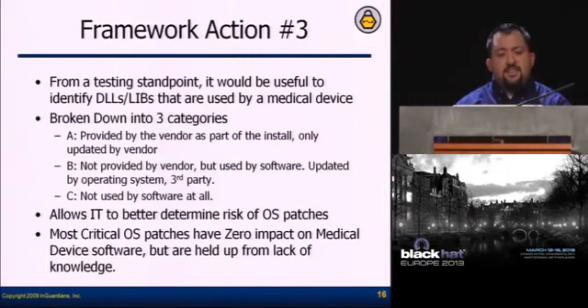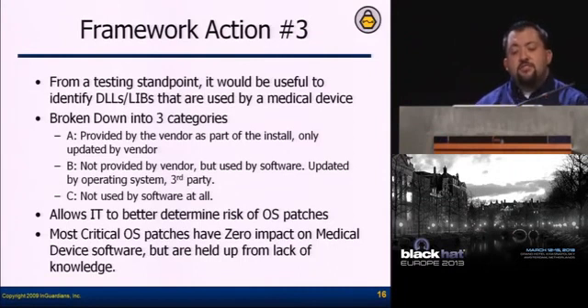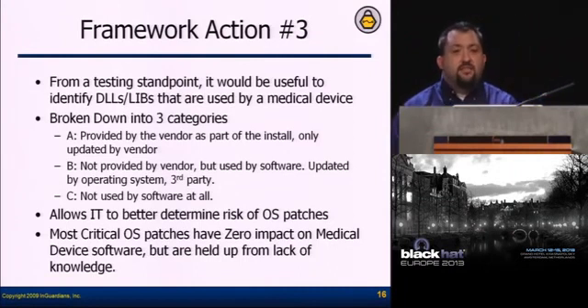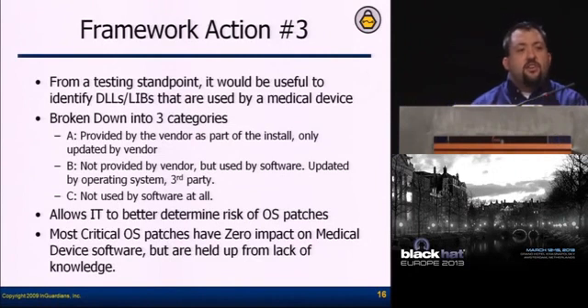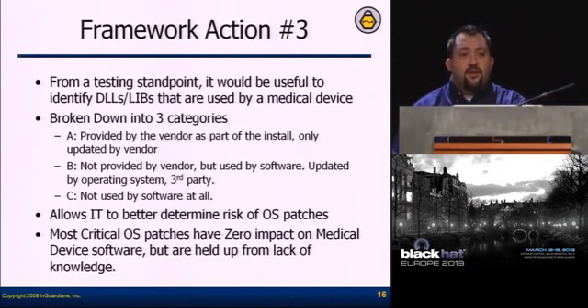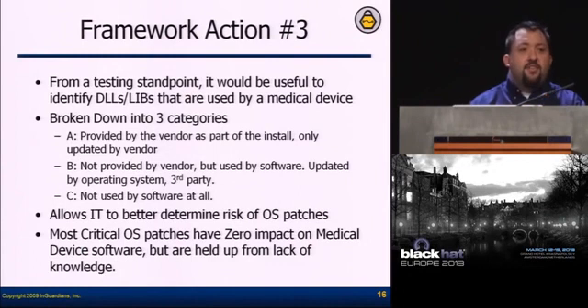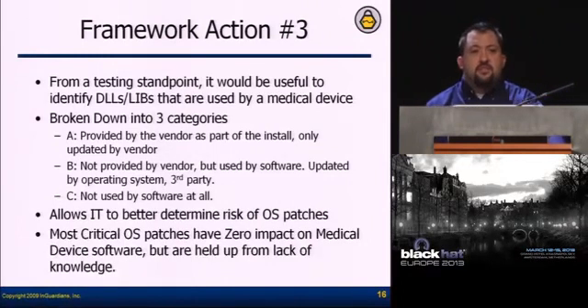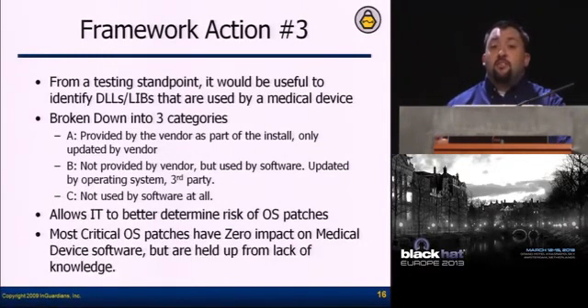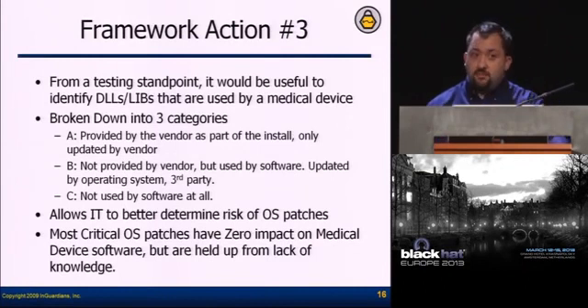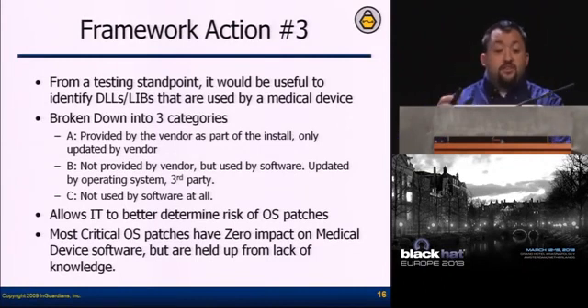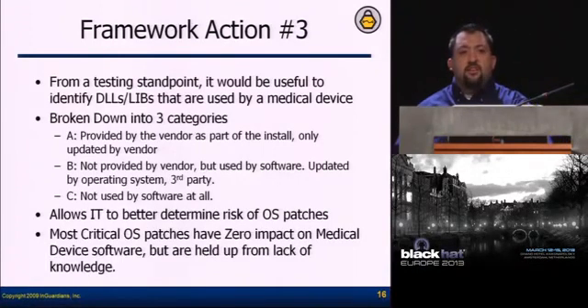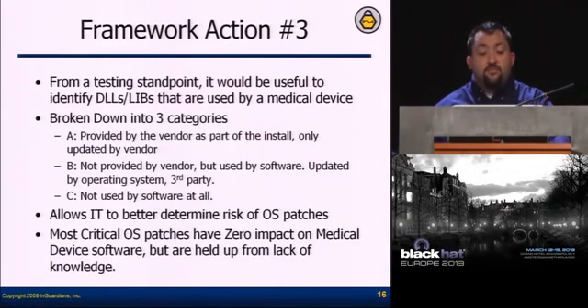This allows IT staff to make better determinations of risk on operating system patches. If you see on Microsoft Tuesday that one of the libraries updated is the one that the Acme MRI software uses, you know that you probably need to do a little more testing before you apply it to that machine. Whereas if all the libraries are in the C class, or there are no libraries in the B class, then you have a little bit more confidence that you can streamline your testing with it in that system.